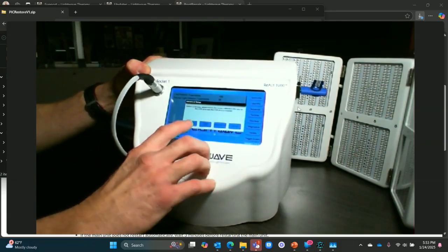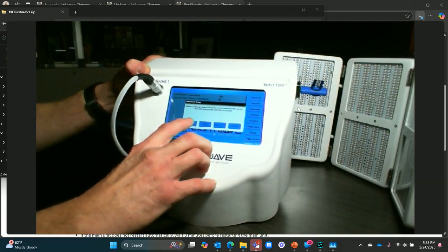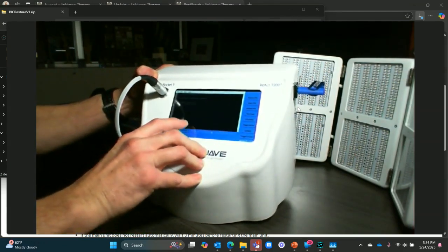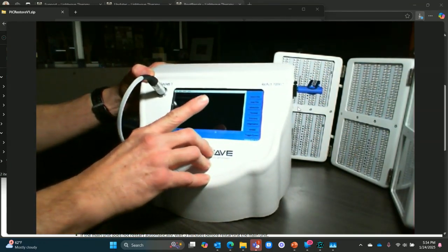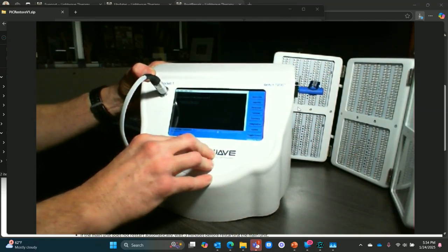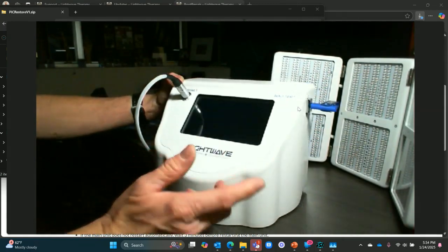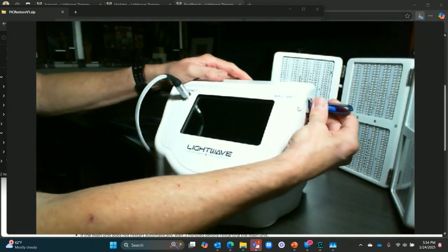I highly recommend. We're going to hit the one called screen calibration. When you hit that, it's going to open up and update the files, automatically reading what's on the USB, those two files that we just put on there. It's going to apply those and automatically reboot. And at this point, while it's rebooting, you can go ahead and remove this.